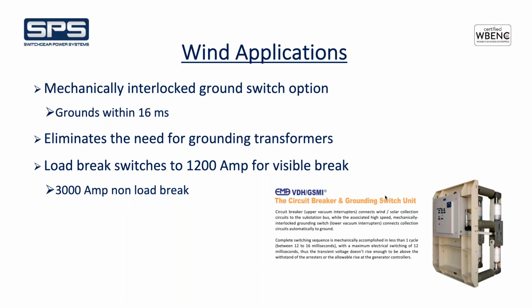So a specific application for the switchgear utilizing the fixed mounted breakers is for wind applications. If you look at this picture, you see that there's two sets of vacuum bottles. Those are mechanically interlocked, and one of them is a high-speed ground switch. When you talk about wind farm designs, traditionally you use either an outdoor station breaker or metal clad breaker in combination with grounding transformers. This circuit breaker allows you to not use grounding transformers, and the ground switch closes within 16 milliseconds of the main bottle's opening, and the same switches we provide for visible break.